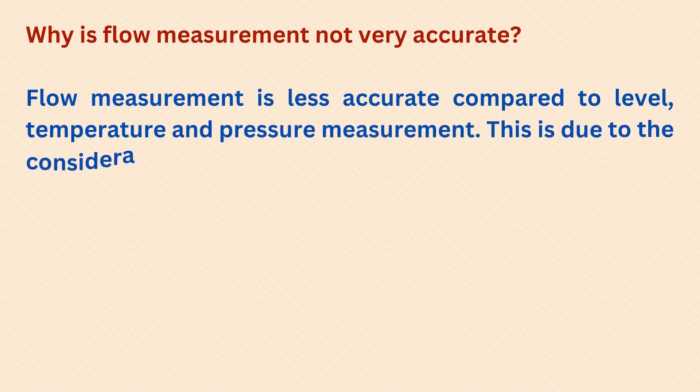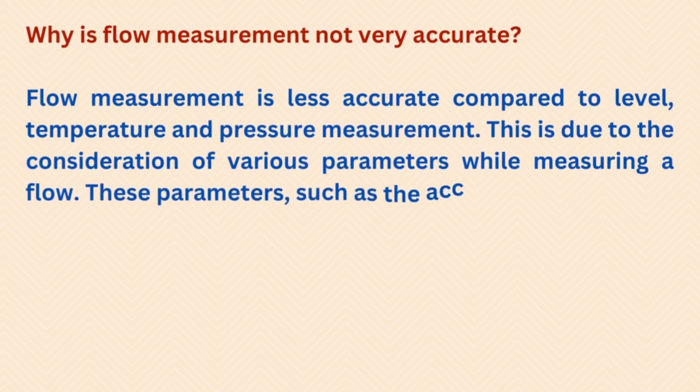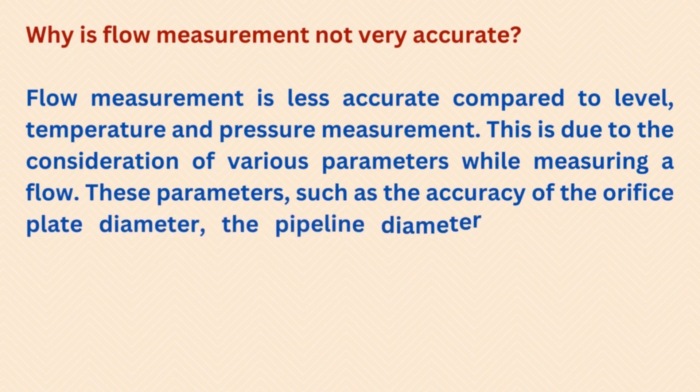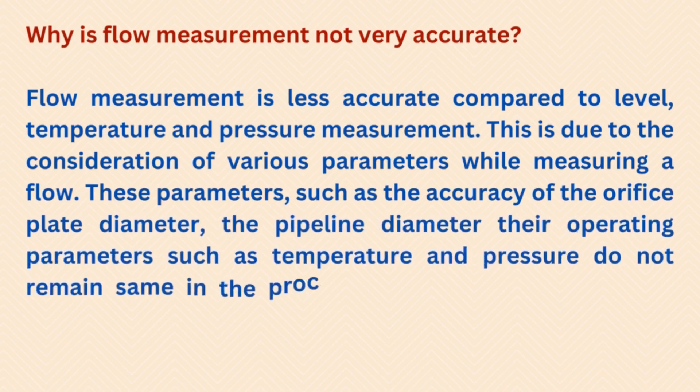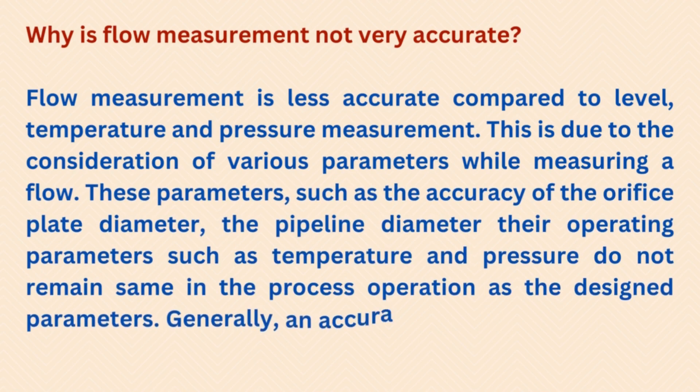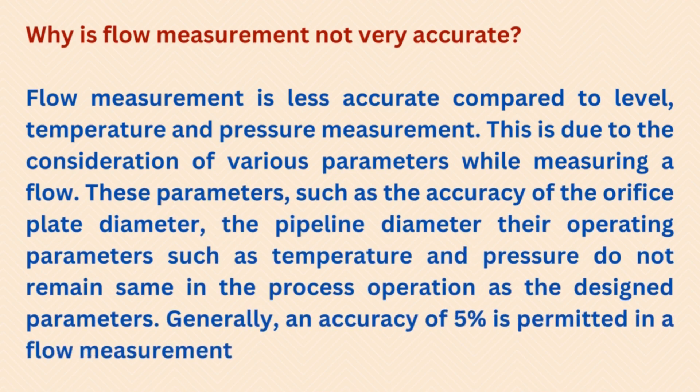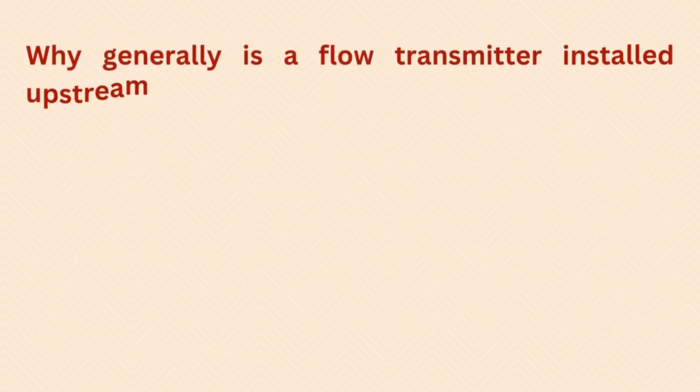Why is flow measurement not very accurate? Flow measurement is less accurate compared to level, temperature, and pressure measurement. This is due to the consideration of various parameters while measuring flow — such as the accuracy of the orifice plate diameter, the pipeline diameter, and operating parameters like temperature and pressure, which do not remain the same as the designed parameters. Generally an accuracy of 5 percent is permitted in flow measurement.